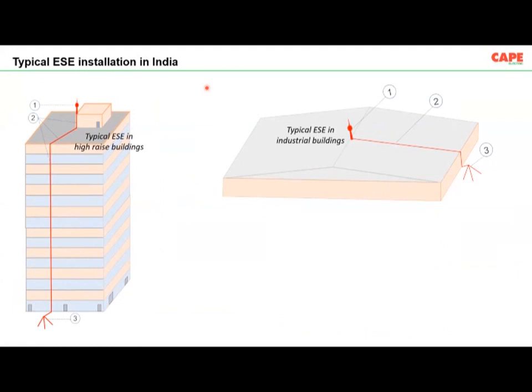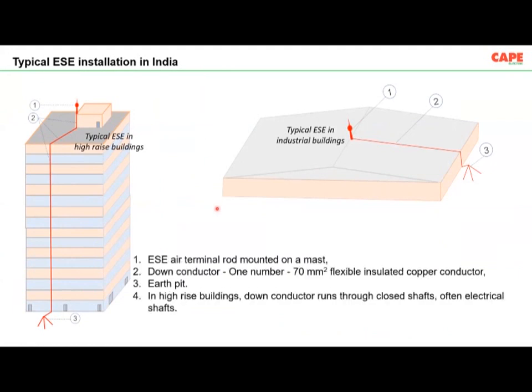But whenever it comes to earthing, what do we do? We have a rod at the top of the building. I'm not saying all the buildings, but most of the buildings. There is an early streamer emission rod at the top, one down conductor and one earthing. Unfortunately, this kind of connection is not recommended in the ESE standard itself.